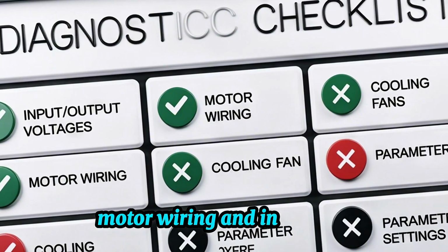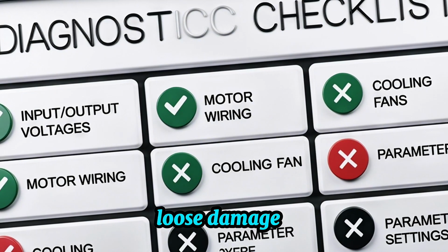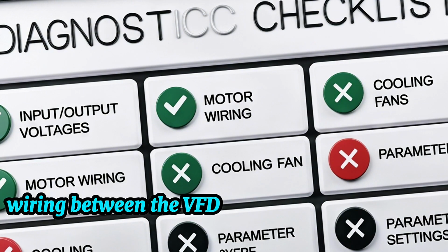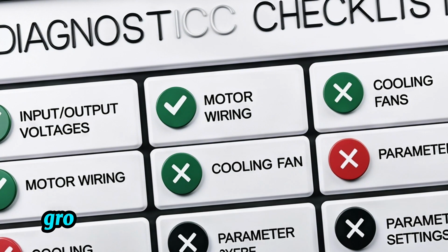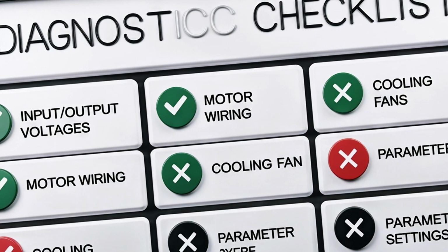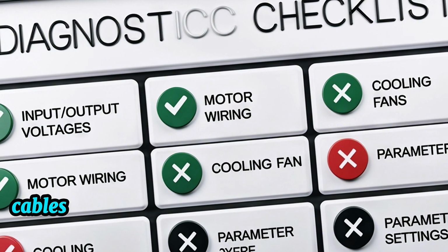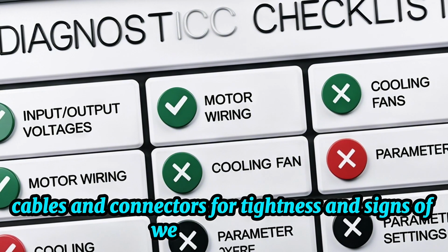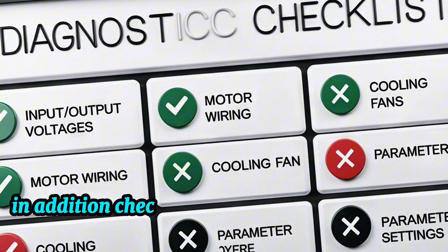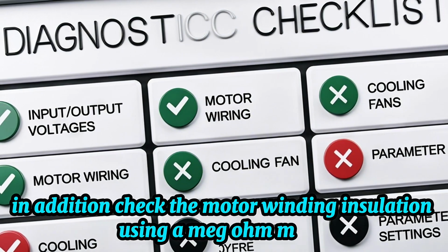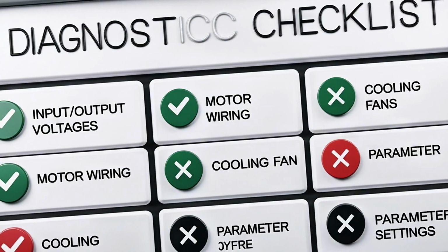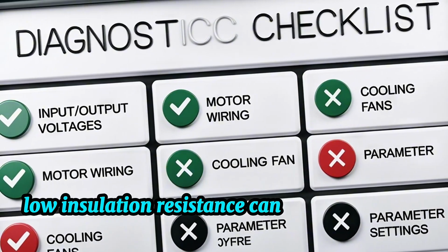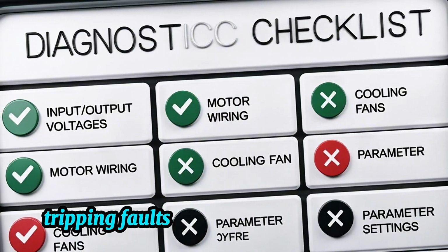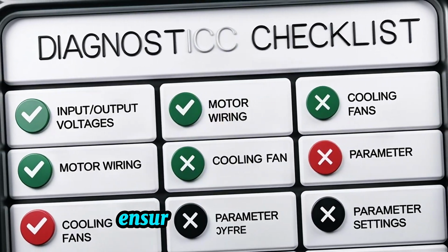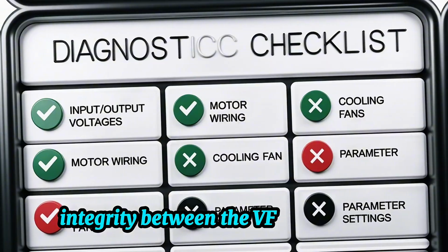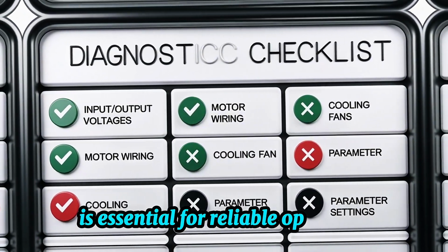Motor wiring and insulation. Loose, damaged, or misconnected wiring between the VFD and the motor can cause short circuits, ground faults, or erratic motor behavior. Inspect all terminals, cables, and connectors for tightness and signs of wear or damage. In addition, check the motor winding insulation using a megohmmeter, an insulation resistance tester. Low insulation resistance can lead to leakage currents, tripping faults, or even equipment failure. Ensuring solid electrical integrity between the VFD and motor is essential for reliable operation.